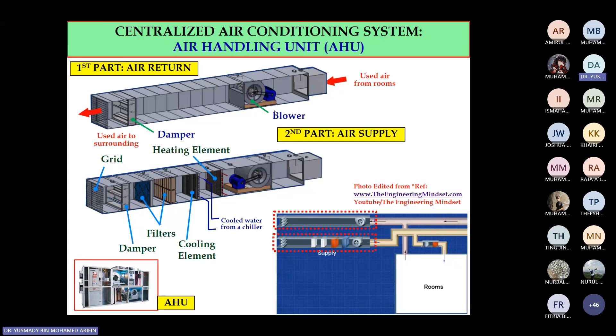The second part we call the air supply part, which is the most important part for the air conditioning system, where we have a number of processes involved. We have a damper to control the volume flow rate. We have a filter to filter any bacteria, any odor or any virus before entering the rooms. We have a cooling element for the cooling process if you want to reduce the temperature of the air, and we also have what I call the heating element if you want to increase the temperature of the air. The blower is used to distribute the air to the rooms. So these are the two main parts of the AHU.